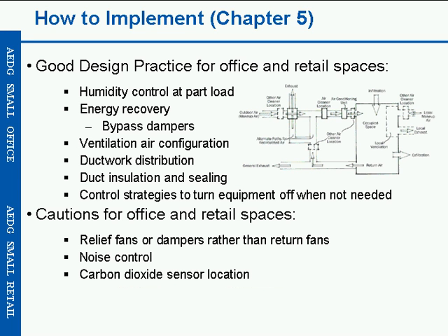As far as how to implement, which goes to Chapter 5, this really looks at good design practice for office and retail spaces, looking at humidity control at part load, energy recovery, bypass dampers, ventilation and air configuration, ductwork distribution, duct insulation and sealing, as well as control strategies to turn off the equipment. It also gives some cautions in terms of relief fans or dampers rather than return fans, noise control, as well as recommendations for where to locate carbon dioxide sensors.